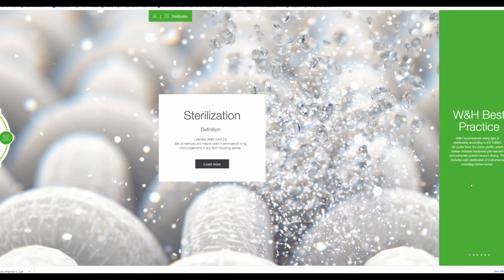First thing, right-hand side, what is here? We recommend, because there are many standards on steam sterilization and different sterilization cycles, we recommend for safety to use B-type steam sterilization cycles, because B-type cycles are designed for any instrument, especially challenging instruments featuring lumens, cavities, tubes, which are very difficult to vacuum, to allow steam to penetrate and sterilize. Obviously, why we need to sterilize, I think this is obvious to all of us. And here are the applicable standards for steam sterilization. Okay, B, N, and S. And here we have the reference standards.